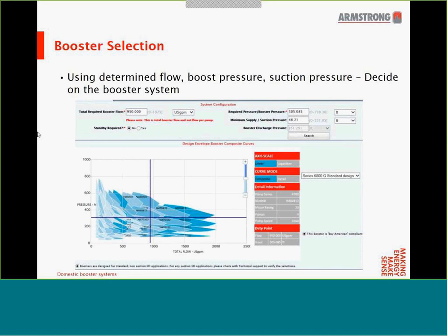Traditionally, sizing boosters was challenging — requiring knowledge of how many pumps, pump horsepower, number of stages, and meticulous review of pump curves. Modern software makes it very simple. As you can see from the screenshot of the selection software, all the booster performance envelopes are included. By simply entering flow, boost pressure, and suction pressure as determined previously, we are given all possible selections. At a single duty point, there are multiple overlapping booster envelopes that can satisfy the requirements. If no selection is available, manufacturers will typically produce envelopes for commonly used boosters, and special configurations can be made for your application.